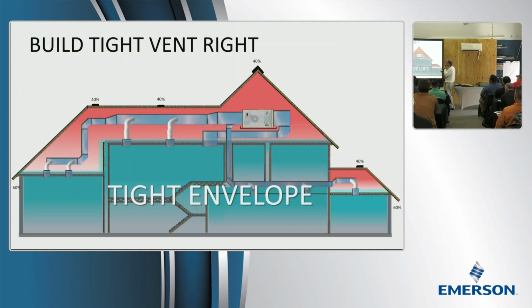If you want to do it right, here's how you do it. You want 1 square foot of opening for every 300 square foot of floor area. And then we want you to put 40% of it at the top, and 60% of it at the bottom. So that is much less than most people have.